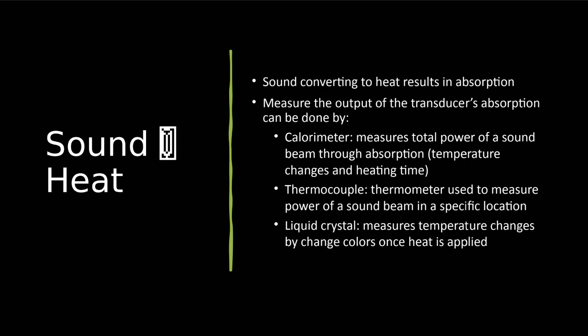As we just said, anytime we're looking at energy conversion, we need to be aware of the effects of that. When we're using this for clinical ultrasound, we know that that is going to result in absorption. The tissue is just going to absorb that heat. We need to measure the output power of the transducer's absorption, and we can do so by 3 different things. A calorimeter measures the total power of a sound beam through absorption, and it gives us temperature changes and heating time. So how fast did this temperature change occur?